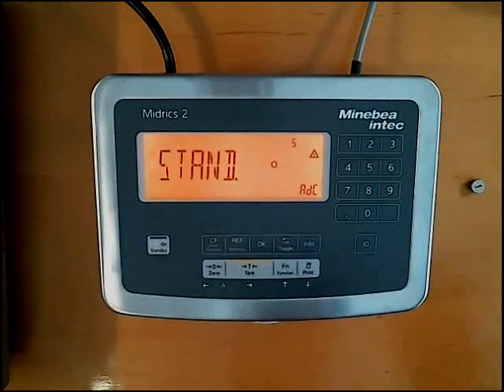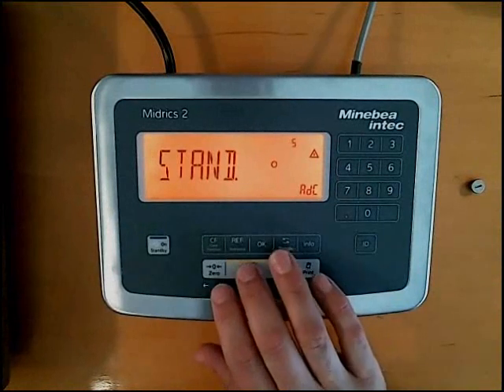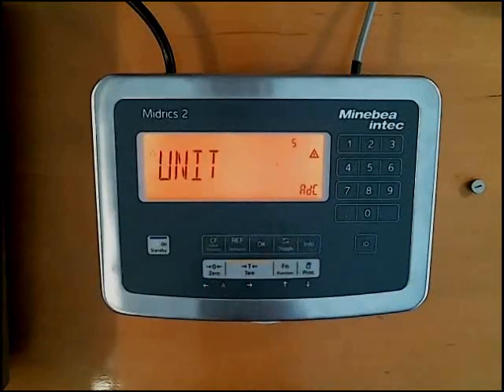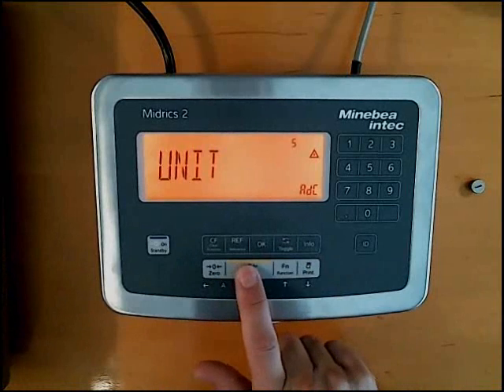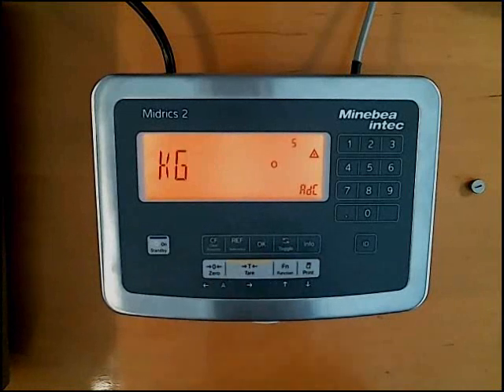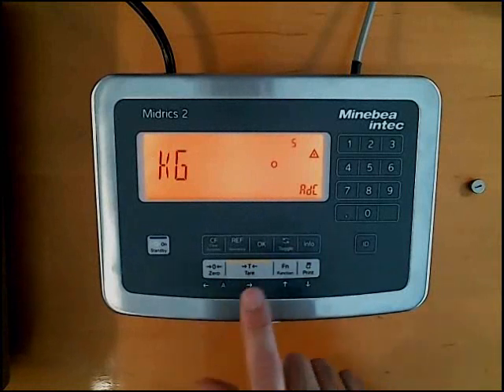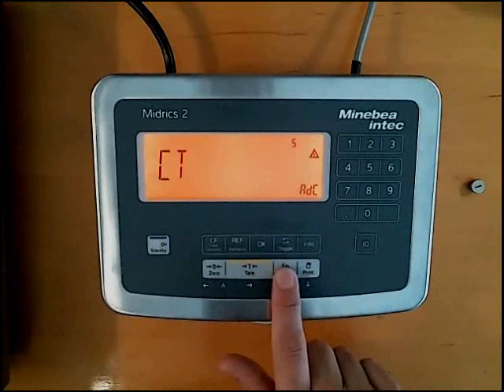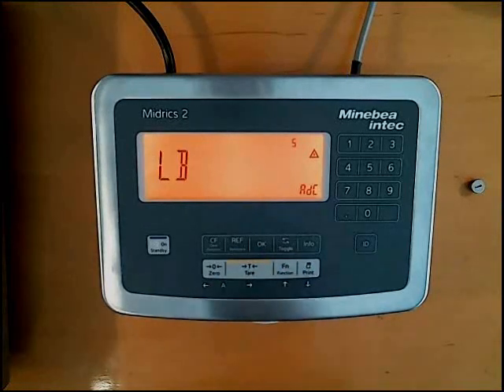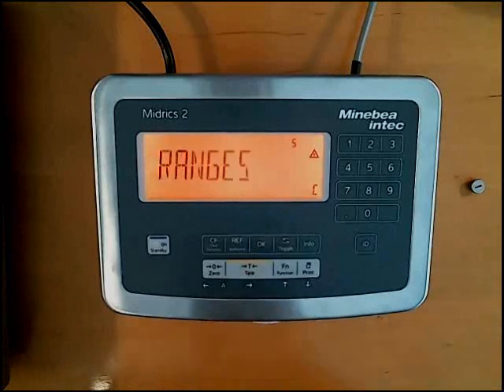Now, the A to D setup is streamlined, so it's going to take you from the beginning all the way to the end without having to navigate the menu. At standard, you're going to push tare. At unit, you're going to push tare. And then you'll see a unit of measure. This unit is showing kg, but I want to set it in pounds. So if you need to change it, go ahead and press and release the function key until you see the unit of measure that you'd like to use, and then press the tare key.